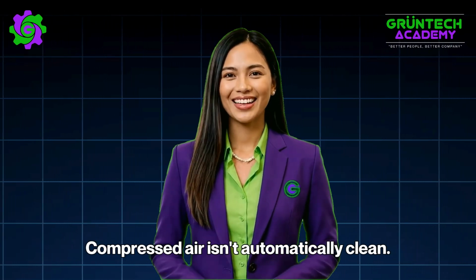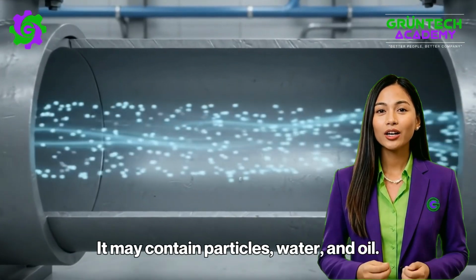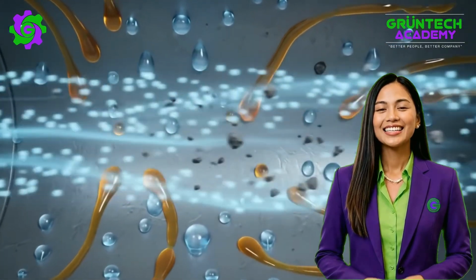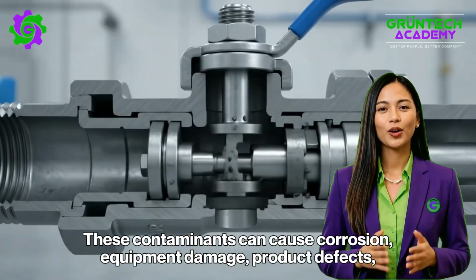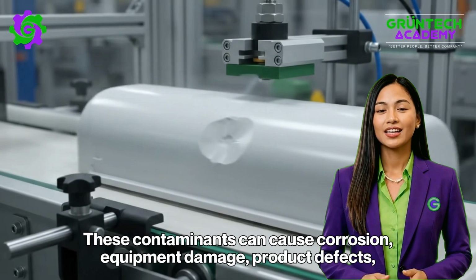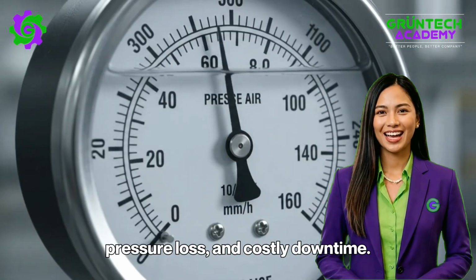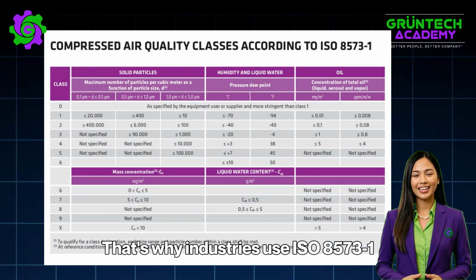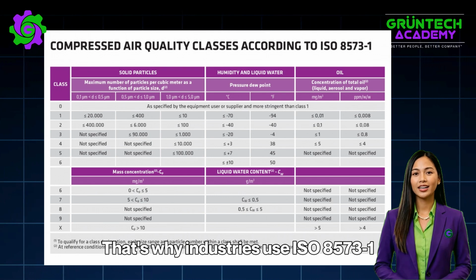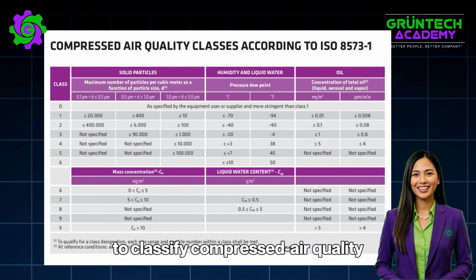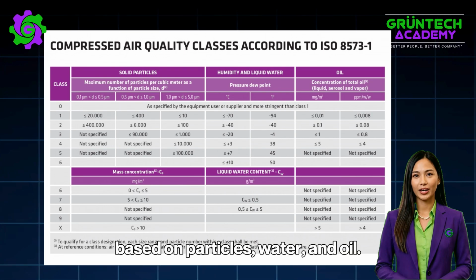Compressed air isn't automatically clean. It may contain particles, water, and oil. These contaminants can cause corrosion, equipment damage, product defects, pressure loss, and costly downtime. That's why industries use ISO 8573-1 to classify compressed air quality based on particles, water, and oil.